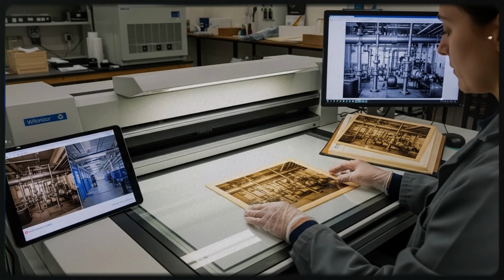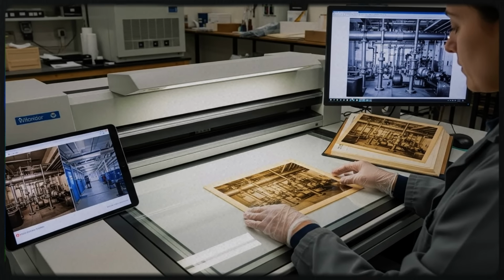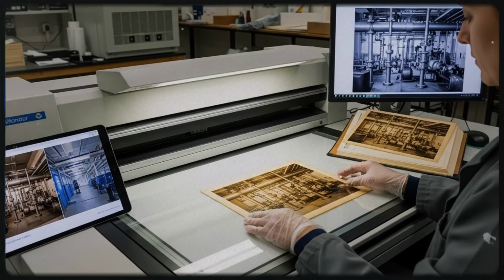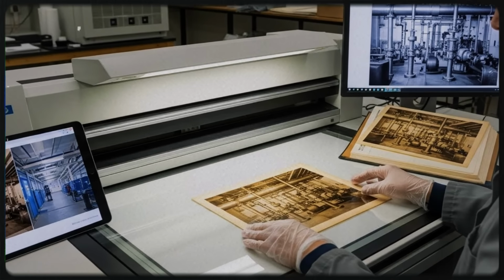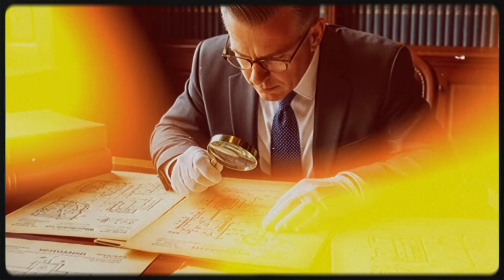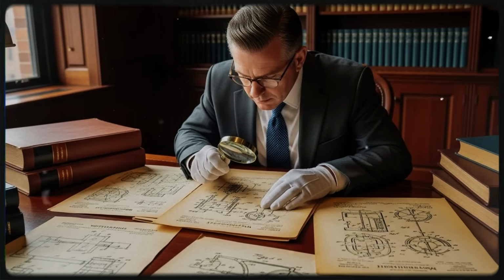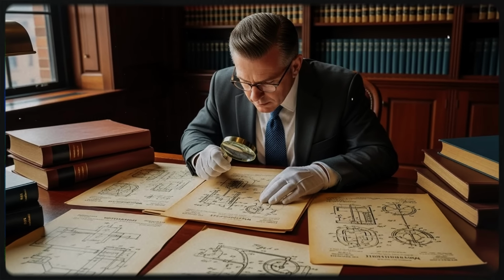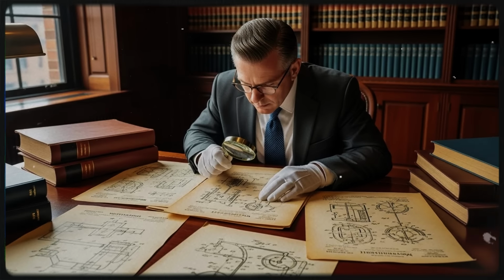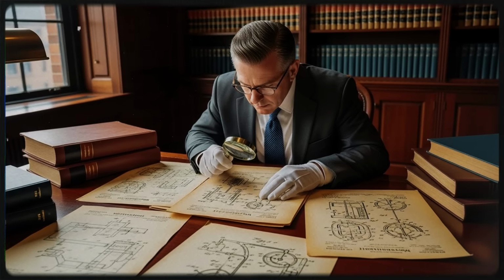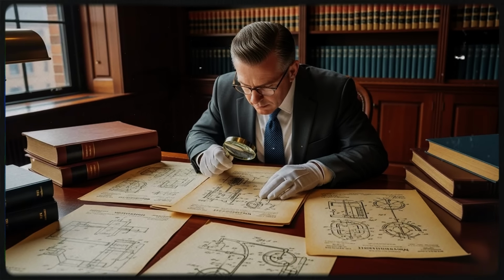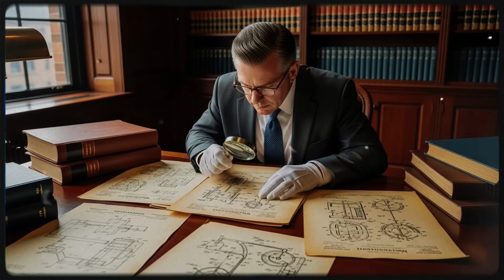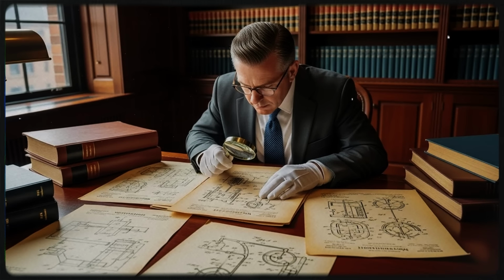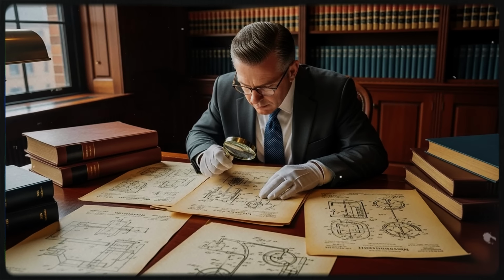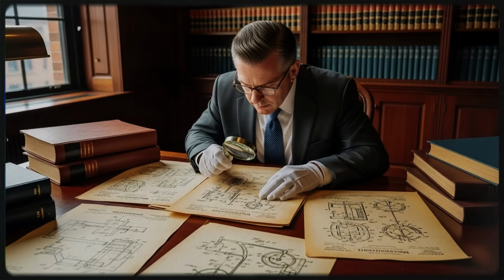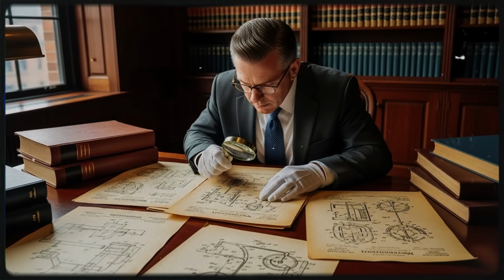Bimetallic element, temperature adjustment mechanism, electrical contacts. The accuracy of well-designed bimetallic thermostats was astonishing. Devices could maintain temperatures within plus or minus 1 degree Celsius of the target. For many applications, including residential comfort and non-critical industrial processes, this accuracy was perfectly adequate. Durability was excellent. Mechanical thermostats installed in the 1920s often operated until they were replaced by digital units in the 1990s.